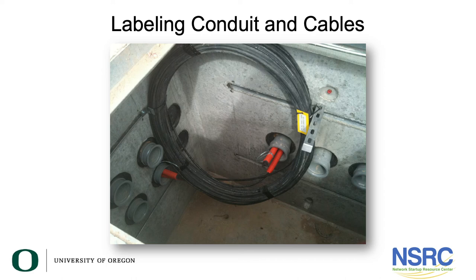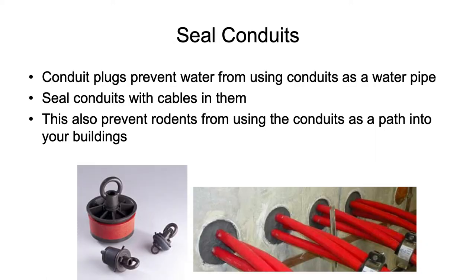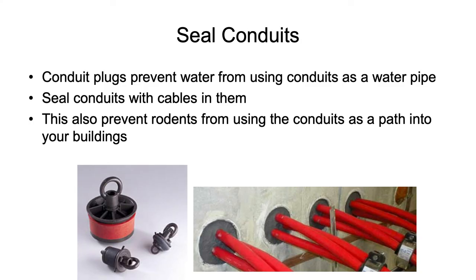For labeling, you can see on the cable itself there's a yellow tag indicating what that cable is, where it comes from, and where it goes. Labels should also be written on the side of the vault indicating where each pipe comes from and goes to. We also want to seal conduits — conduit plugs shown on the left are inserted at the end of the pipe; turn the little knob to waterproof it and prevent rats from using the conduit as a path. For pipes with existing cables, use grout — the same material used between bricks — to seal the pipes against water and rodents.